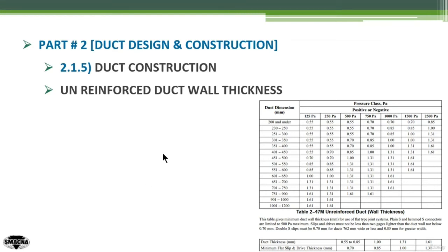Ducts can be either reinforced or unreinforced. For ease of illustration, we will start with the small tables for unreinforced duct sheet wall thickness. After obtaining the pressure classification of the duct, this becomes the entry key for the following table, which is used to specify the sheet metal thickness of the duct.